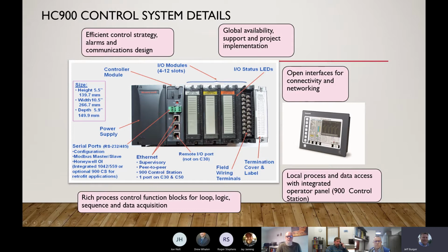The very bottom port is for the remote I/O. So you can have additional remote racks hooked up to the single CPU, and if you have processes that are spread out through different areas in the plant, you can have one CPU communicating to these additional racks that would allow the I/O to reside next to the process. So it'd be a little bit easier for troubleshooting, diagnostics, and doing work right at the local piece of equipment.